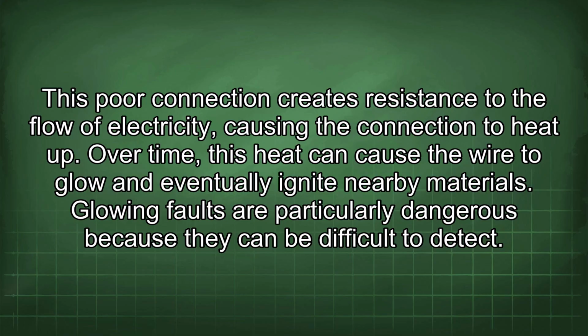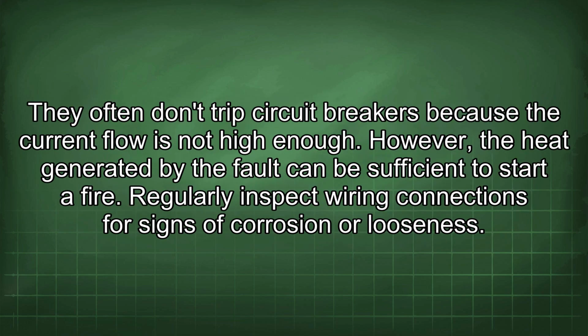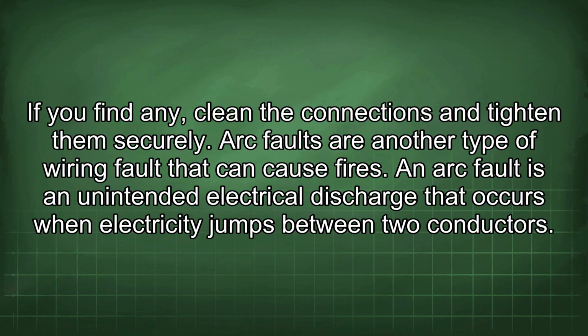Glowing faults are particularly dangerous because they can be difficult to detect. They often don't trip circuit breakers because the current flow is not high enough. However, the heat generated by the fault can be sufficient to start a fire. Regularly inspect wiring connections for signs of corrosion or looseness. If you find any, clean the connections and tighten them securely.